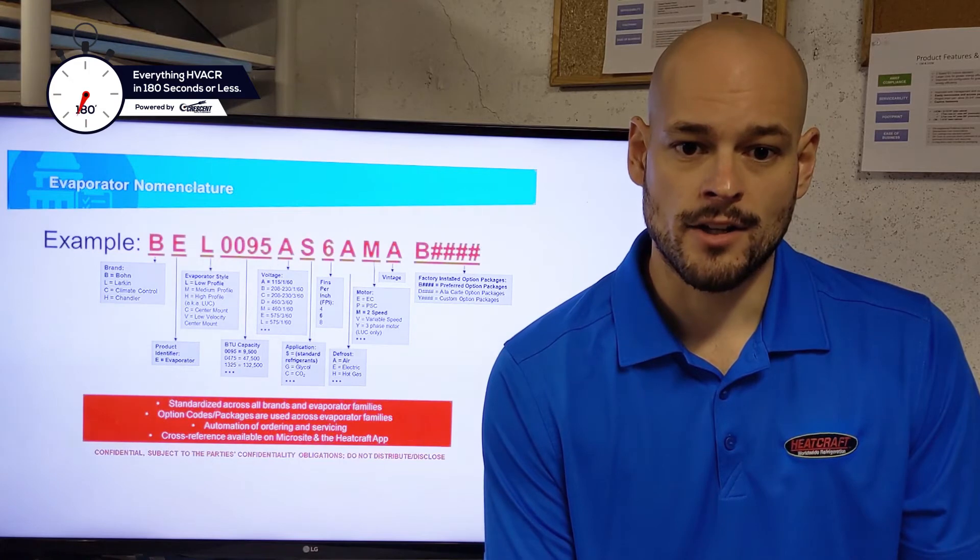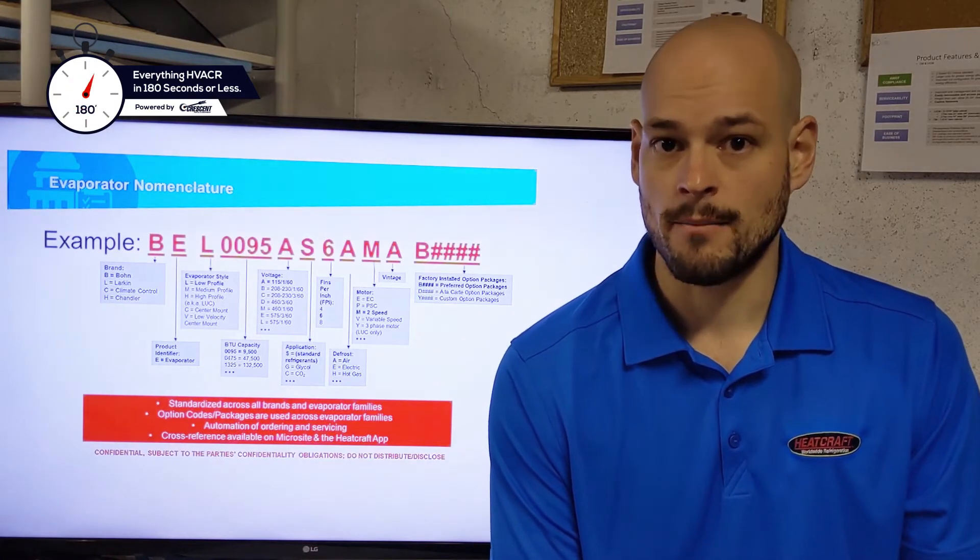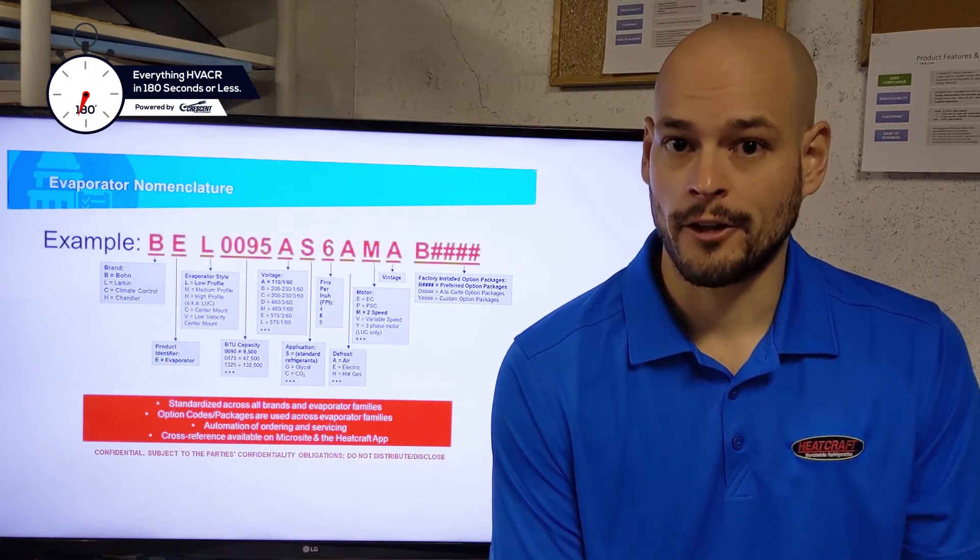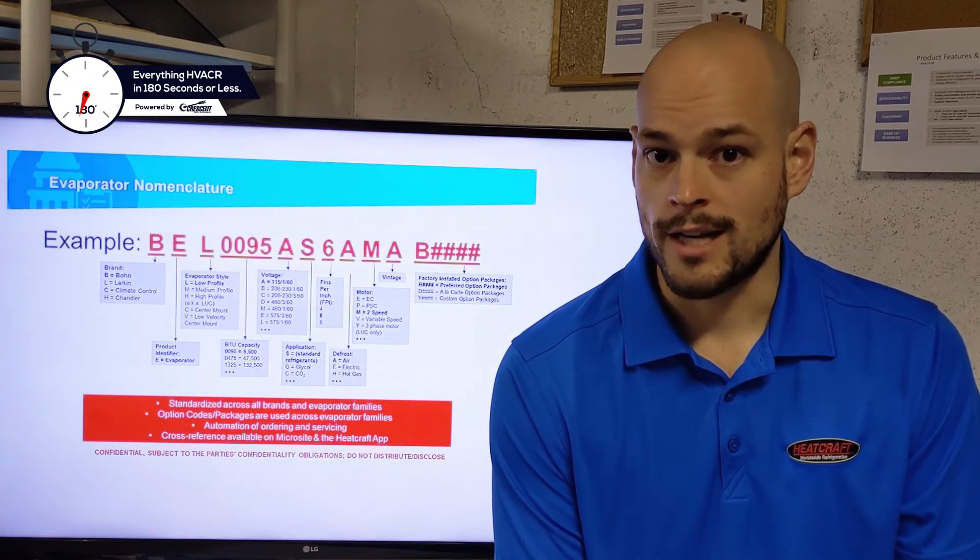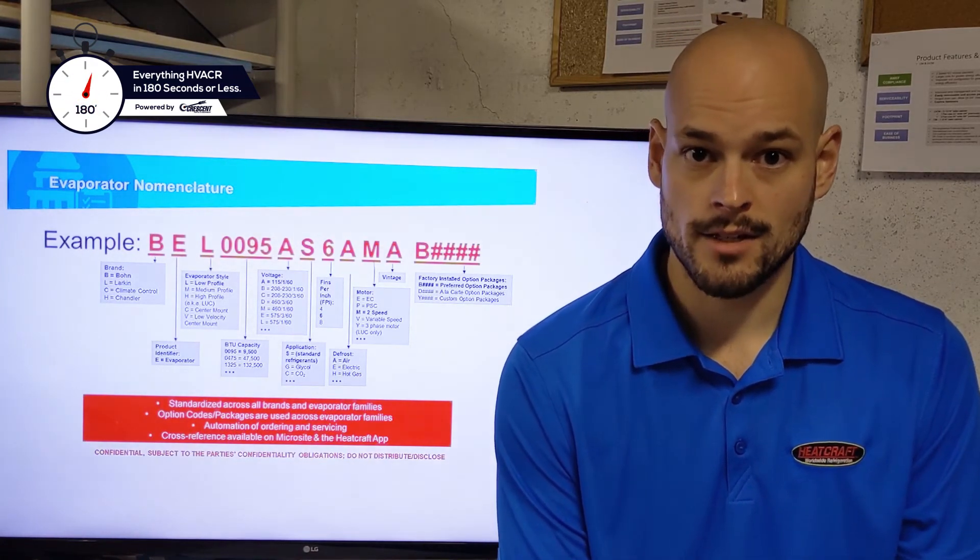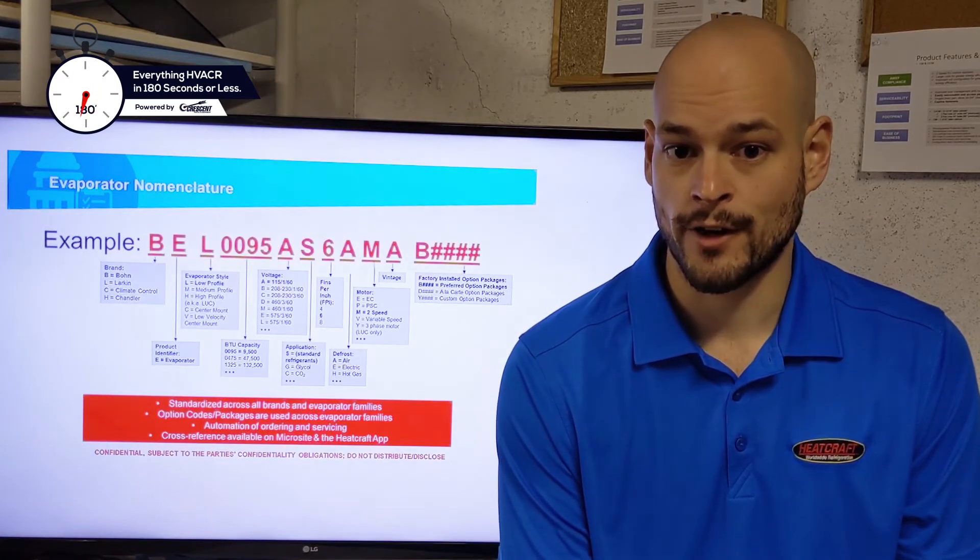Your next indicator is going to be your defrost code. Really simple. It's going to be an A for air, E for electric, or H for hot gas. Your next code is going to be your motor. E for EC, P for PSC, M for two-speed, and V for variable speed.